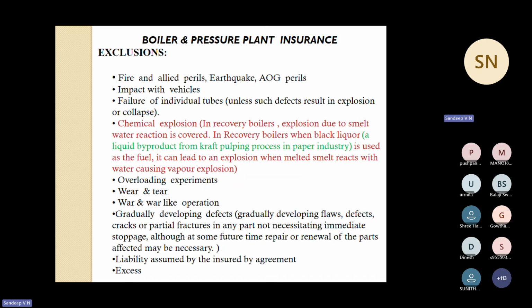Black liquor is a mixture of many items, including a chemical in wood known as lignin. It can lead to an explosion when in contact with water, since water droplets accidentally dropping onto the combustion chamber cause a sudden increase in vapor pressure, creating an explosion. This type of explosion normally happens in a waste heat recovery boiler. It is not treated as a chemical explosion but as a smelt water reaction, which is covered under the policy.